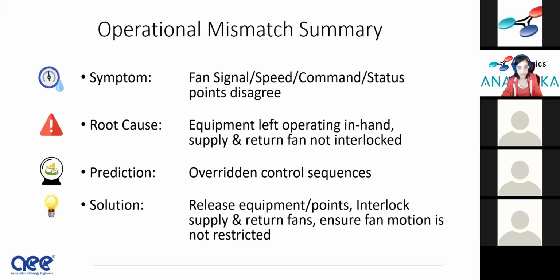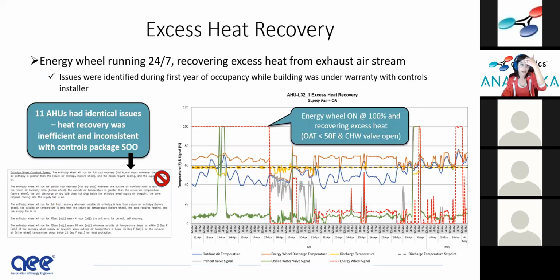Also check to see that fan motion is not restricted. If your speed is less than your signal implies, then there might be a restriction there. And again, that really does lead to equipment degradation if it's restricted in some way. It's not operating how it should be. You could have increased heat and things like that. Last example, I swear, is excess heat recovery. This is more of an analytics example, but I wanted to include kind of a complex sequence of operations example.